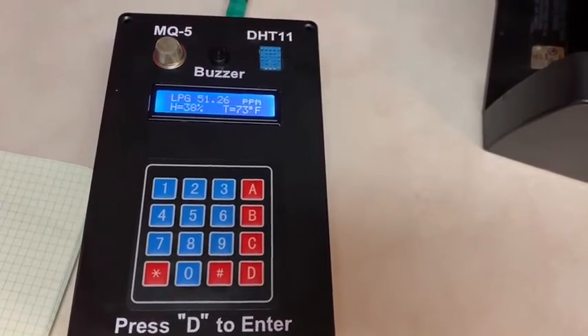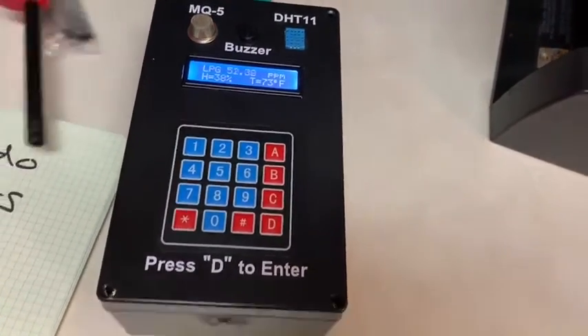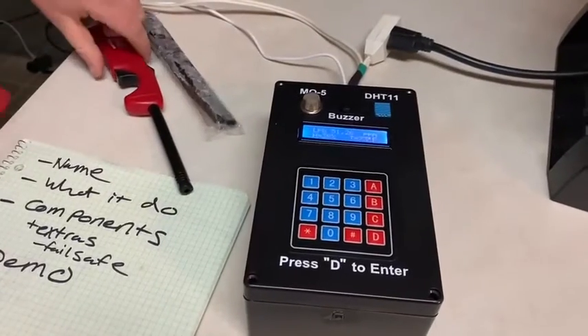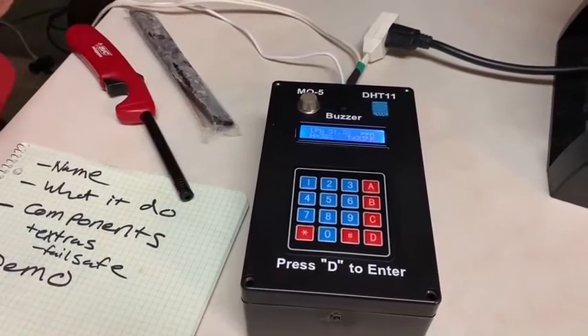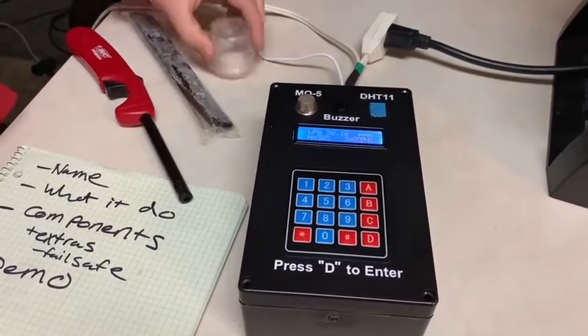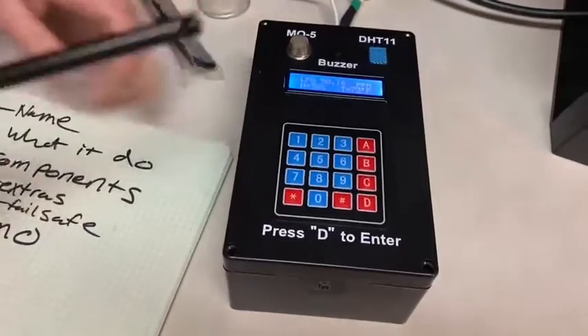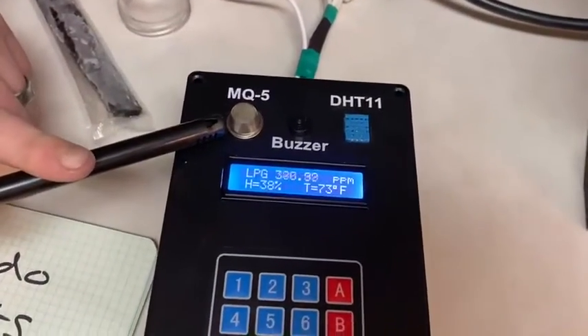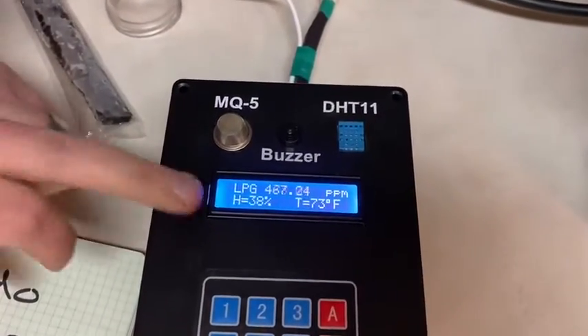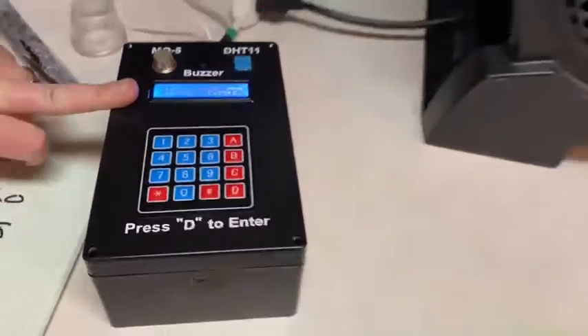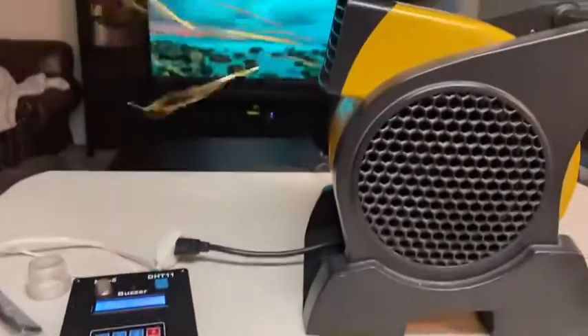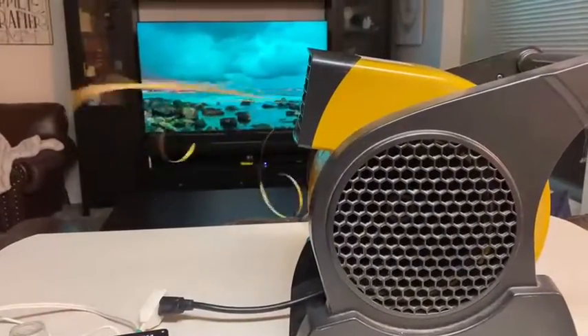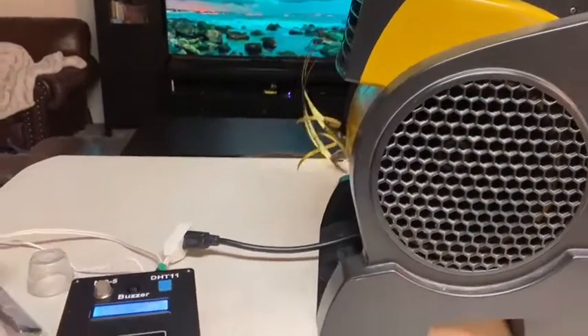For the sake of time, I have a couple tools to help me. So what we'll do is simulate a gas leak. I've got a lighter here, and once we exceeded 300 parts per million, the ventilation fan turned on until it started detecting below that limit.